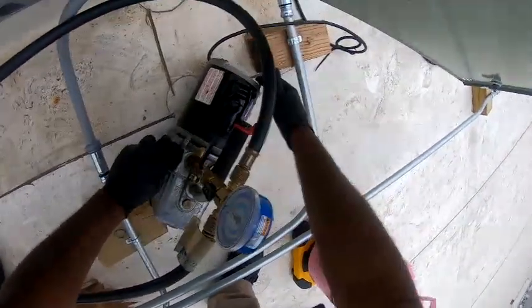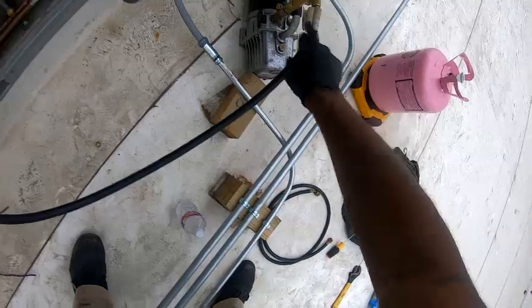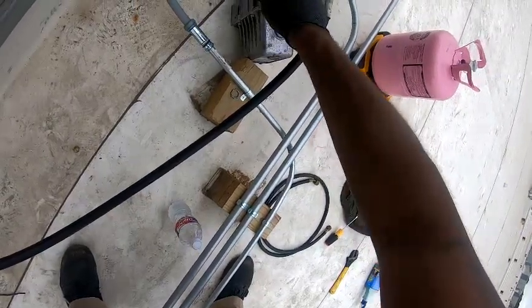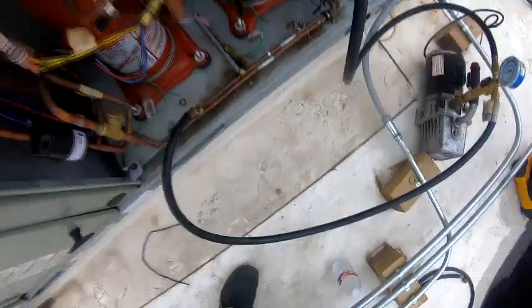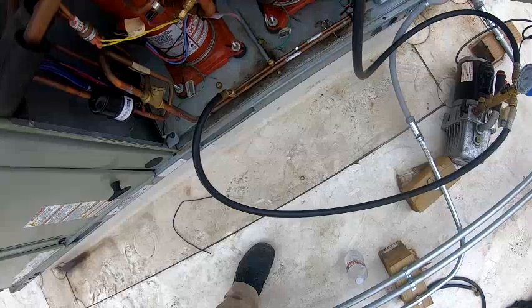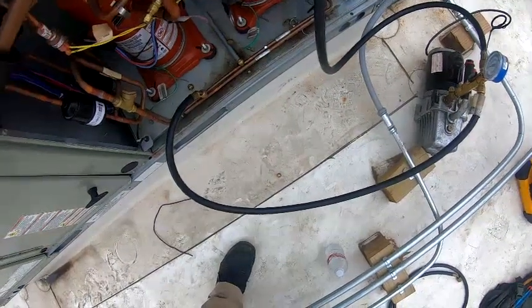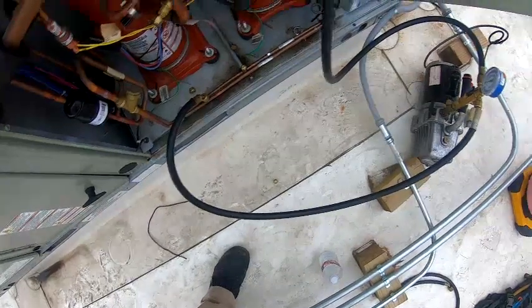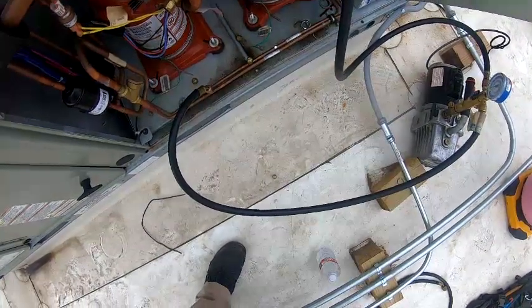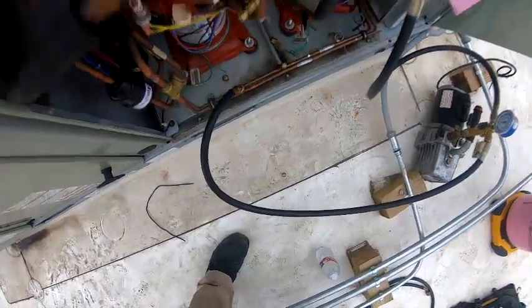So I can just go ahead and turn that off. Right now I've just cut the valve out to the vacuum pump. I still have it open for the micron gauge. Like I say, typically you want to get it down to 500. Right at 500, it's all good. Really, as long as you've got it below 1,000. But get it down to 500 microns and isolate the micron gauge.